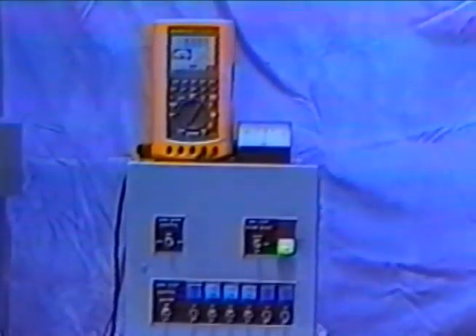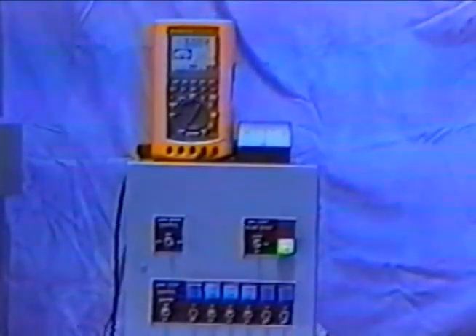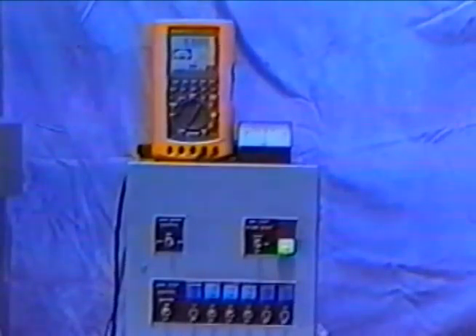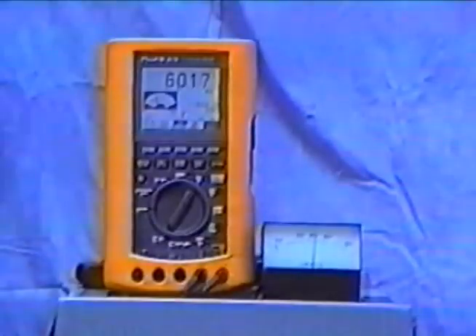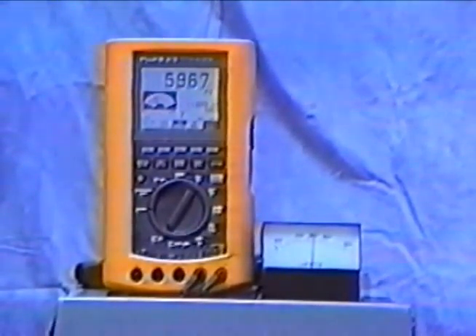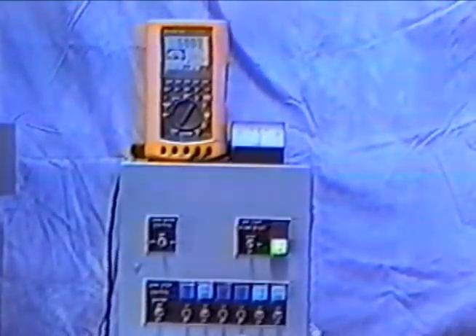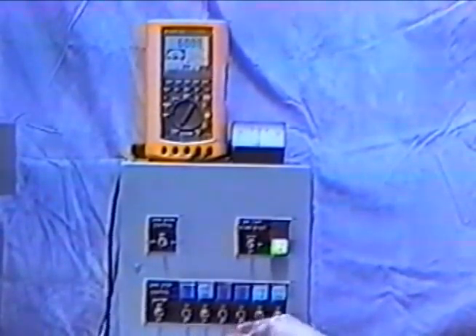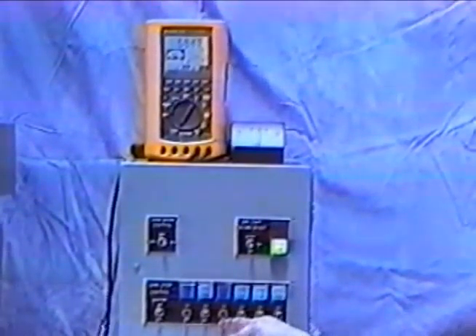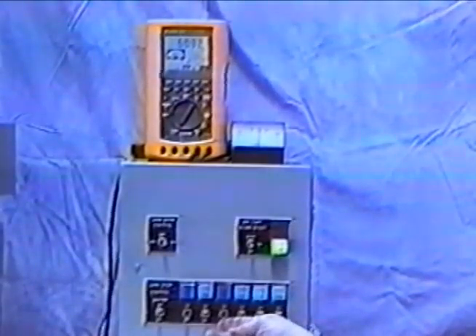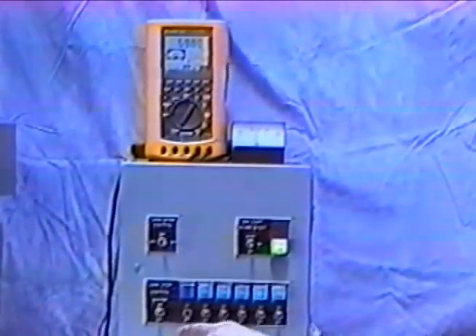This represents an actual load bank test performed in our test cell. We have used 2 industry standard cycle meters to demonstrate the Innovator stability. Here we show the Innovator in a steady state environment. Setting new standards in process control, the Innovator control is capable of updating 40 parameters every millisecond. The processor instantly commands the unit's various skid-based hardware. Here is a demonstration of normal load changes.